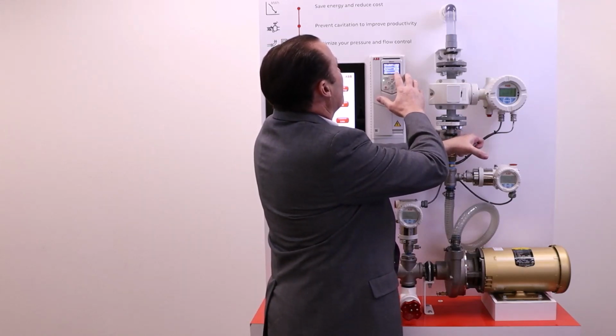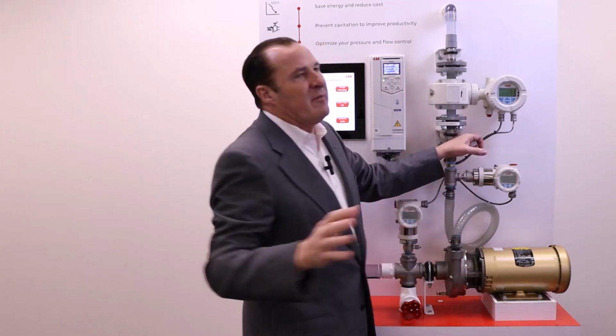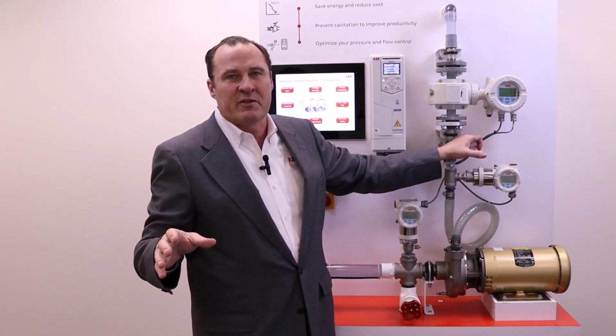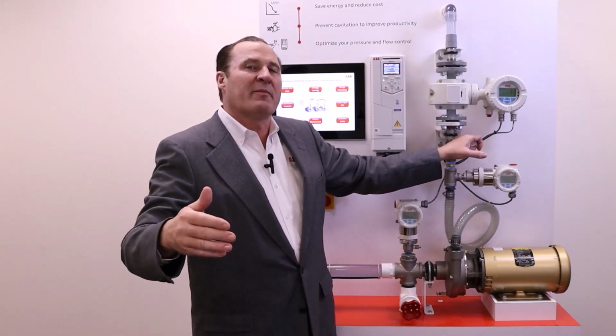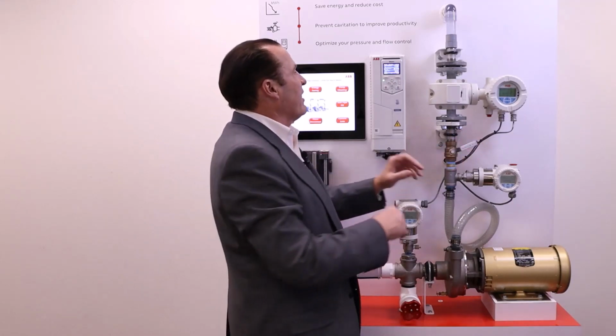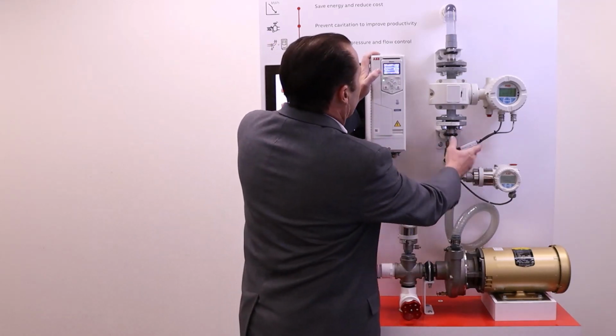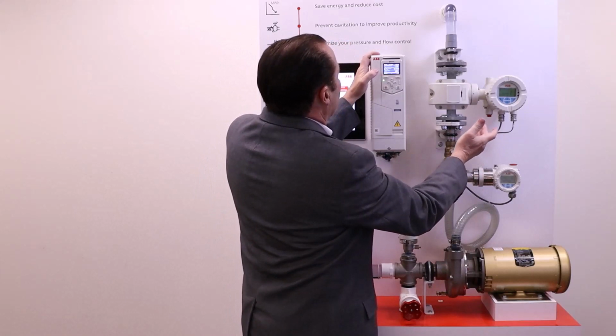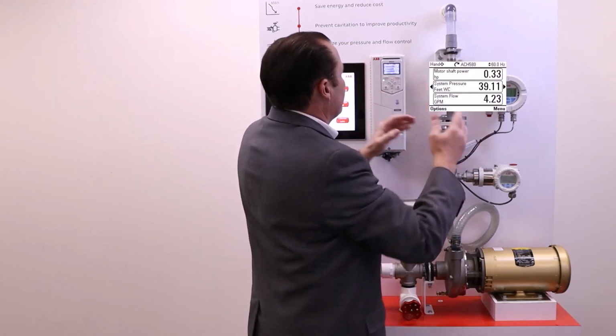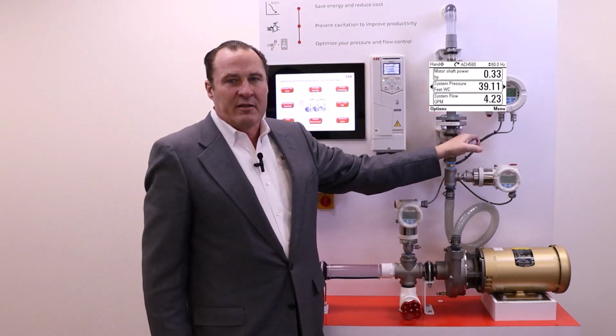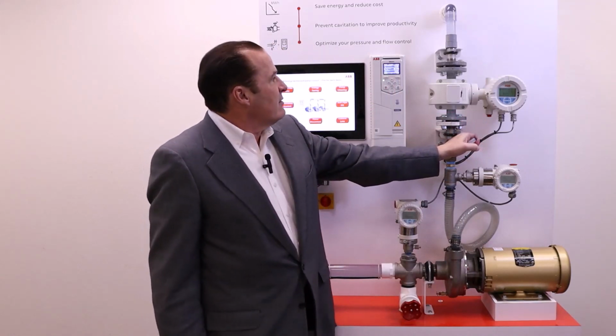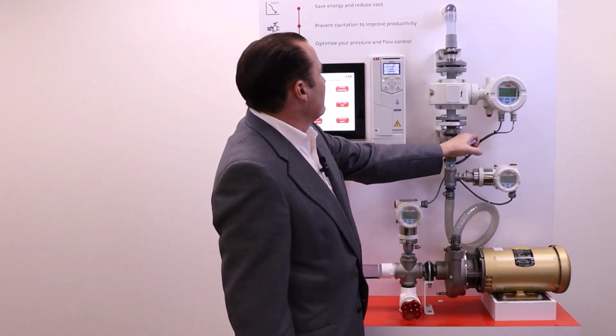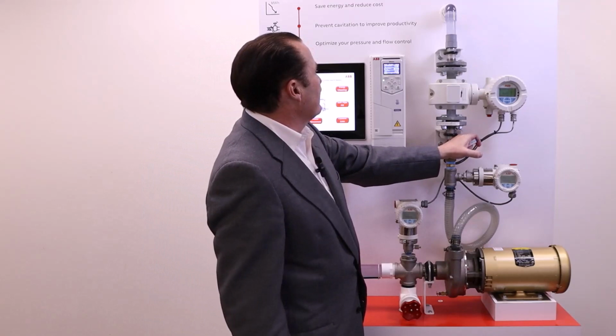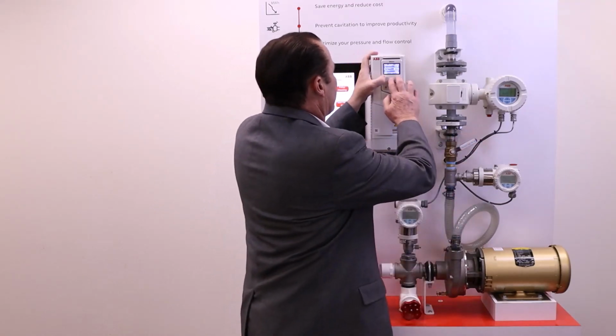When I get my flow around 4.22, remember, you don't need your data points to be perfectly accurate. You just want to break them up so you have 10 data points. I get that flow around 4.22, let it stabilize. At that point, I do another screenshot. I continue on. Next point is 8. So I go up to around 8, let it stabilize, and we'll do another screenshot.